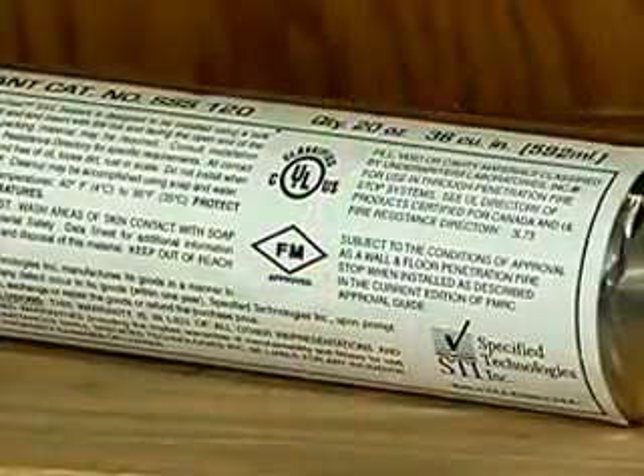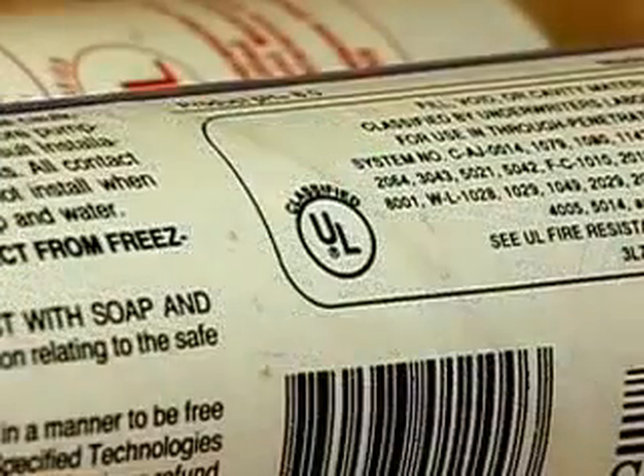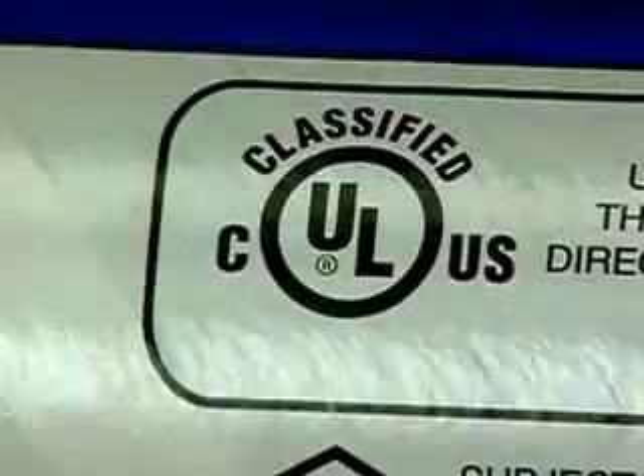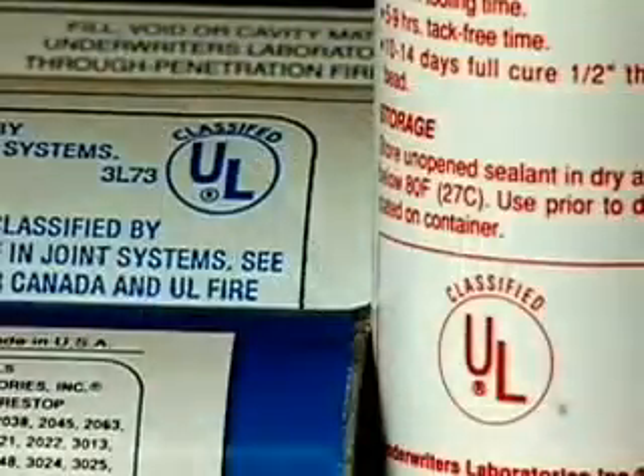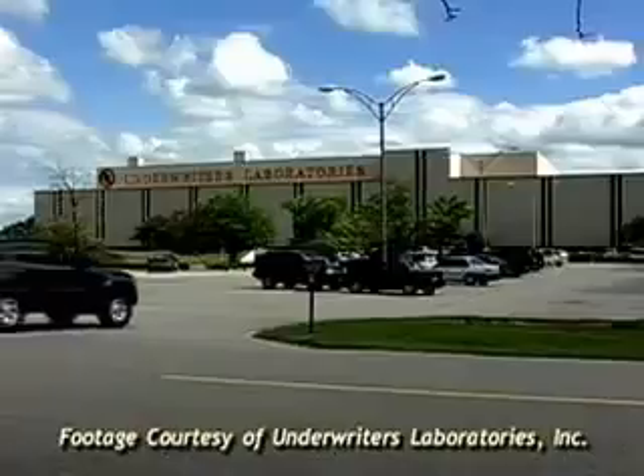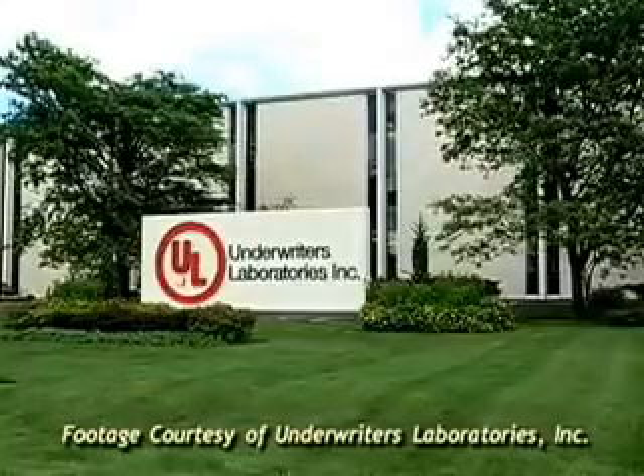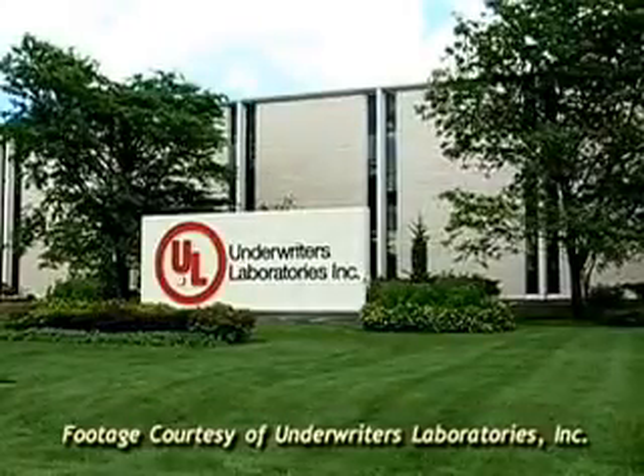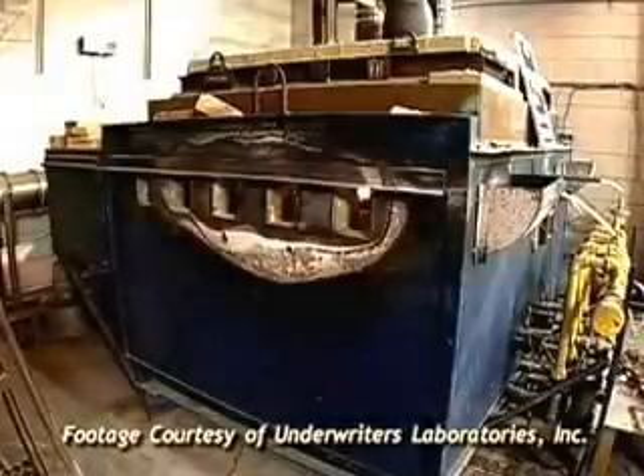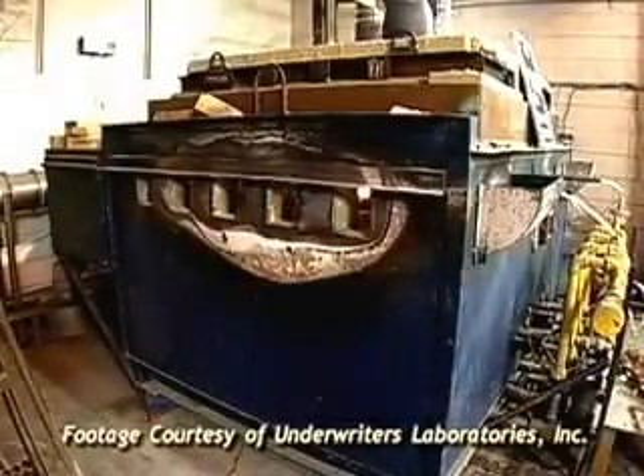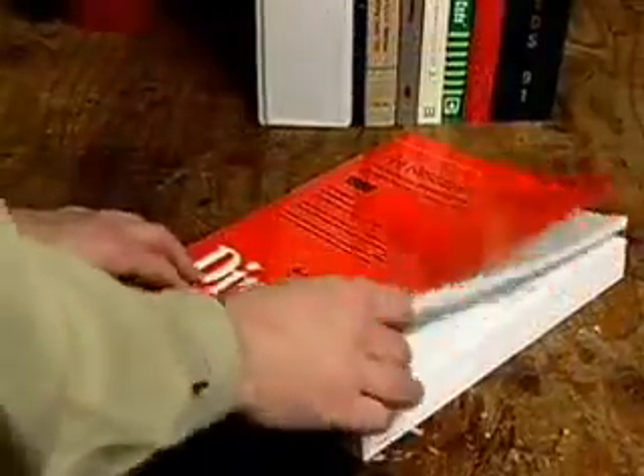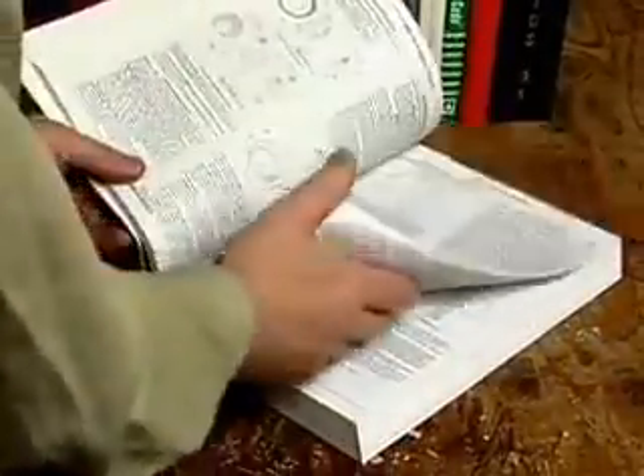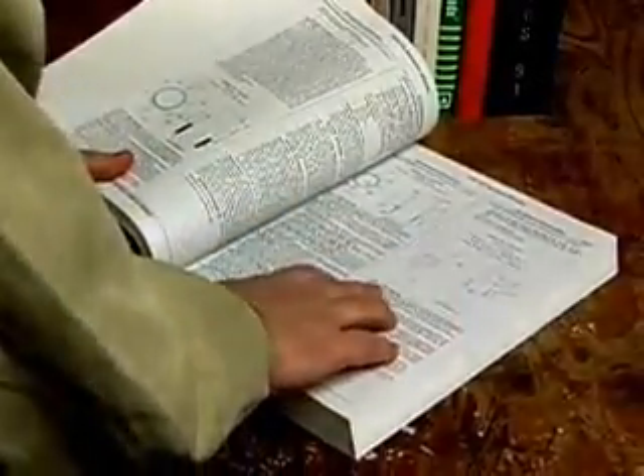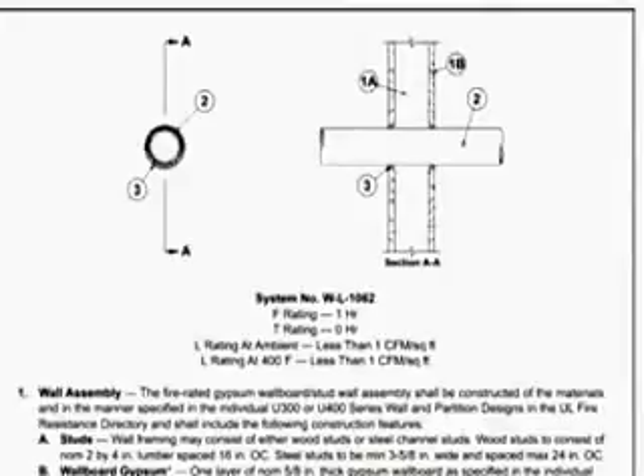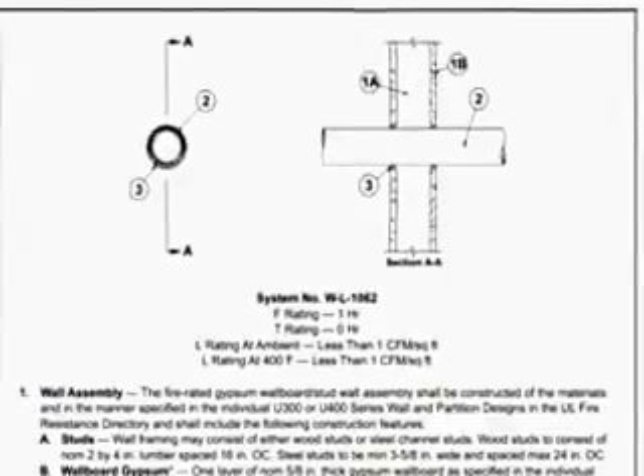Many installers mistakenly assume that simply having a UL logo on the tube offers adequate compliance. This misconception can be very dangerous. Each manufacturer of Firestop is required to test their products in a furnace at a third-party lab such as UL to determine if their products actually work in the presence of fire. When a test is successful, the lab issues documentation that permits an installer to use that material only in the application tested. This documentation becomes the evidence of compliance to an authority having jurisdiction.